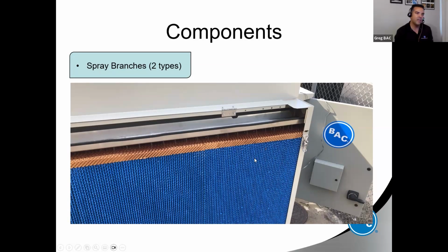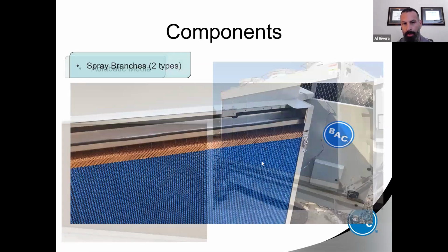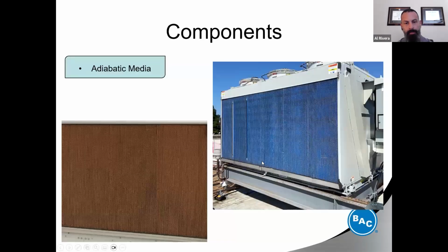And I know that doesn't sound like a big deal, but it makes a huge difference. I mean, you basically lose like 50% of your capacity just by doing that. And we have seen it many times when the pads get installed. Dry spots in the pads. Yeah, dry spots in the pads will also contribute to increased scaling too. So it's not just efficiency, but also a potential maintenance item.